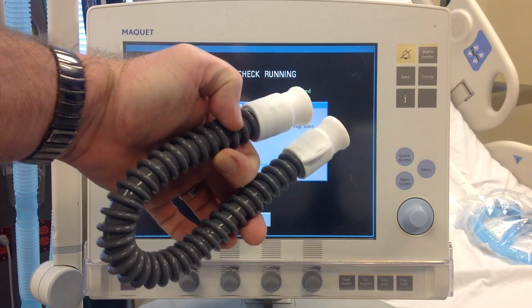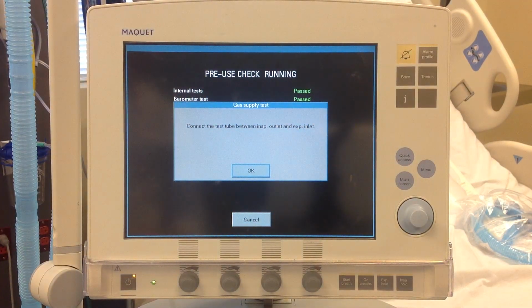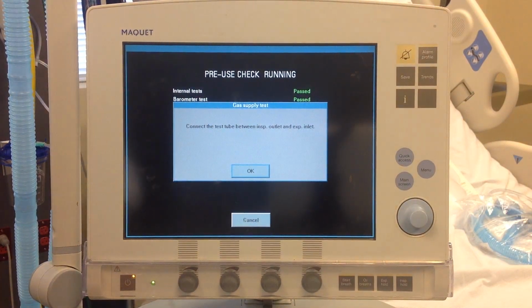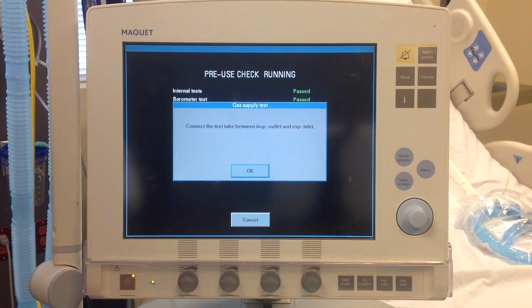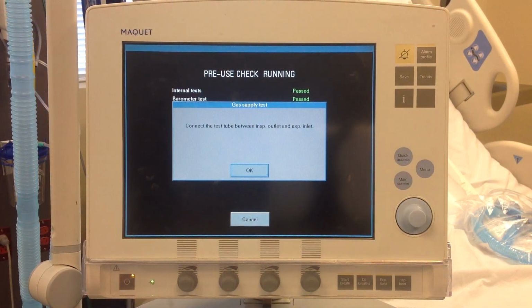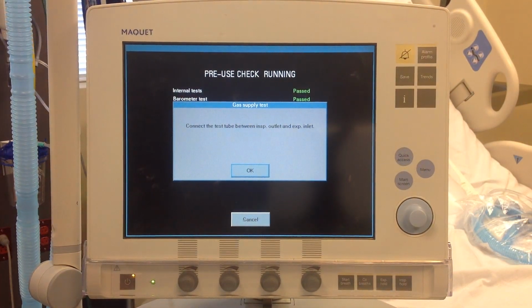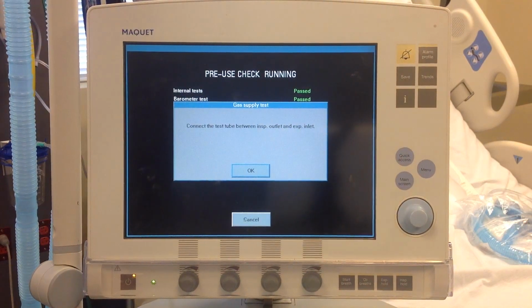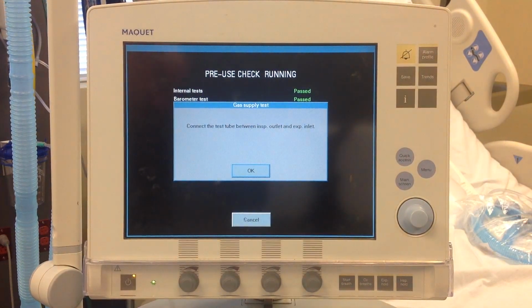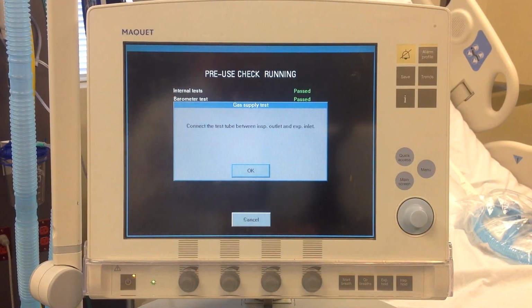It looks something like this, and this is supplied by Maquet. You cannot just use a hose that is supplied or that you cut off of a roll of large bore corrugated tubing. They say that the machine knows the compliance and stretchability of this hose, therefore you have to use it. Remember, when pushing anything on the exhalation cartridge, to support the exhalation cartridge.